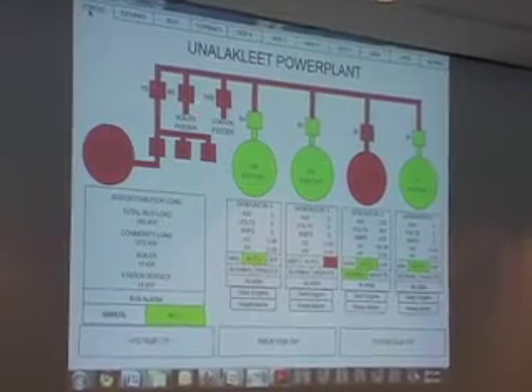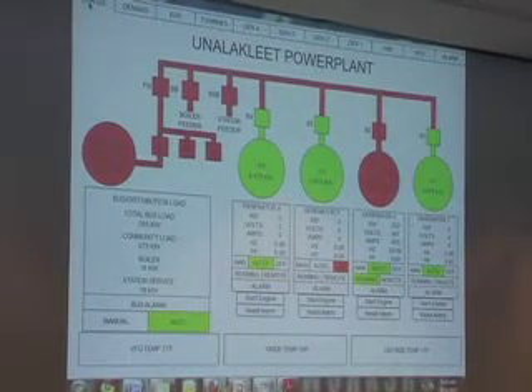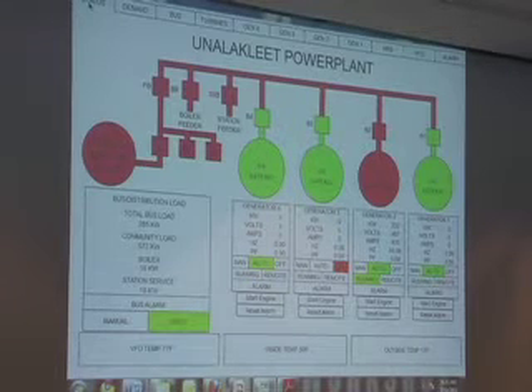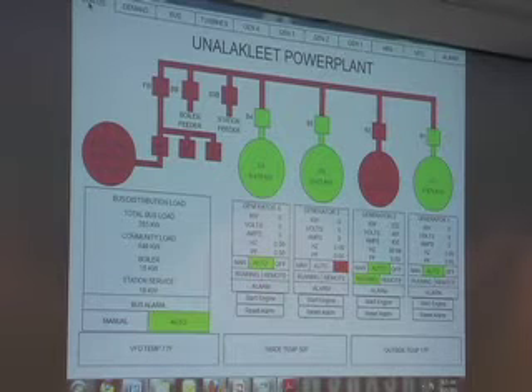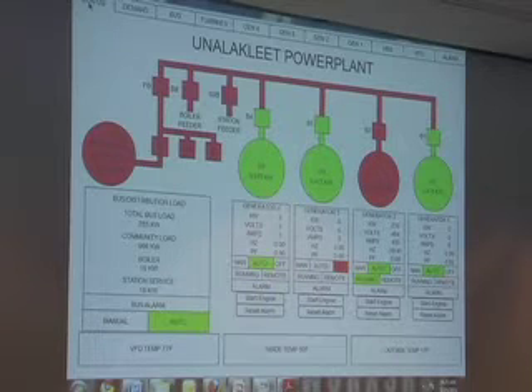The boiler, what we're experimenting with right now and working with Northwind, is allowing the boiler, we kind of pick a set point, and it helps stabilize the grid. It moves up and down, but we don't ratchet the boiler up in load unless the diesel generators, we have like a 20 kW deadband. So that way we stop the diesel engines from hunting all over the place, trying to follow the wind around. So if the wind's pretty steady, we try to keep the diesel generators within a 20 kW band. And if the wind dies down, then we pull load from the boiler, and then we step that down, and the diesels can ramp up. But that's kind of our PID loop right now on this.